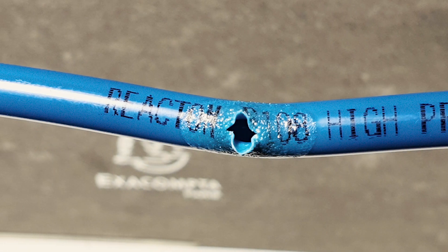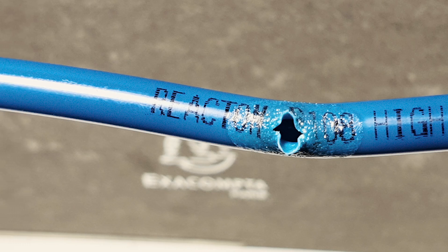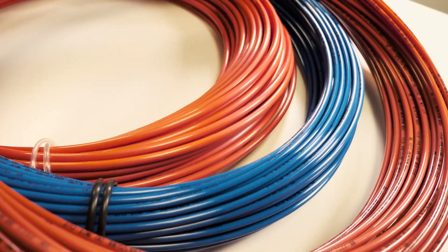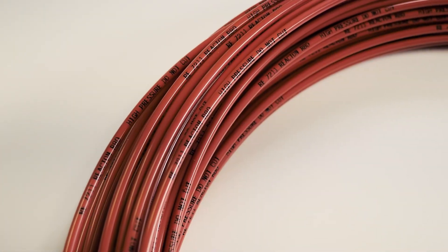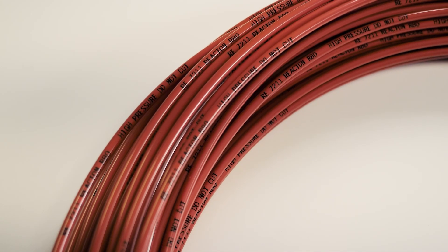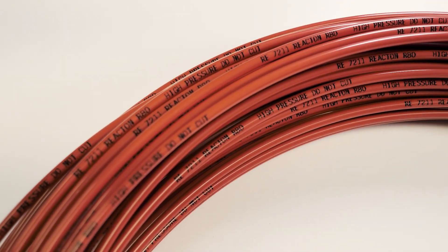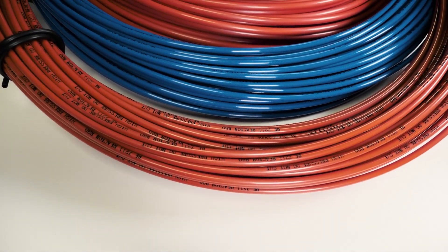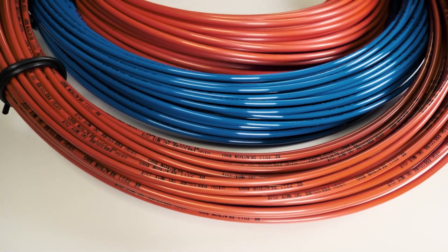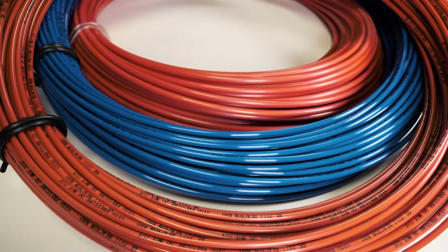The Detection Tube is designed from a heat-stabilized proprietary polymer to rupture at a specific temperature when subjected to the radiant heat of a fire, available in various grades to suit either sensitive electrical risks or the harsh environments found in a vehicle engine bay, providing the perfect balance of rapid detection without false alarms. It will not be affected by dust or debris and does not require any power to operate, meaning you have confidence in true 24/7 protection.